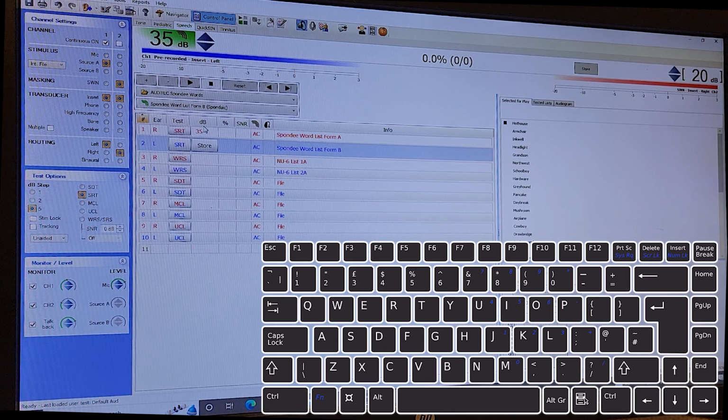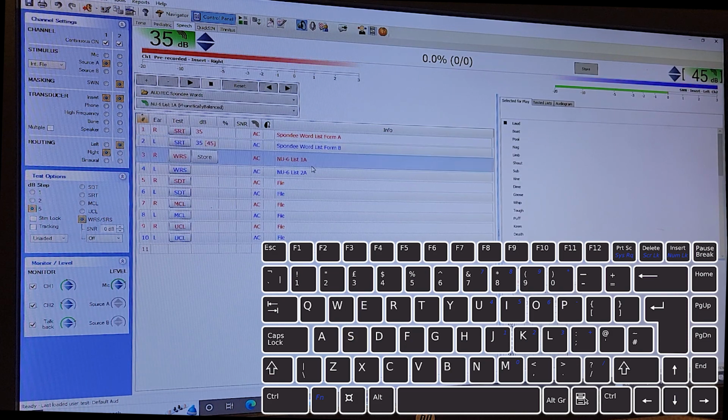If you need to mask, you would hold shift and change what masking level you want, then press M to present the masking. And again, if you need to change your masking, you just hold shift and use your arrow buttons up or down to change your masking level. You can continue to present with your F5 mode. House. And if you want to save your masked results, you will need to have your masking on when you save. Otherwise, it will save as unmasked. So if you save here, you can see that you have your masking level saved as well.